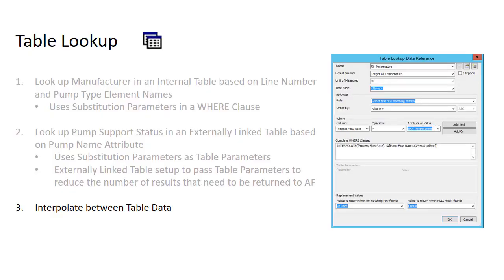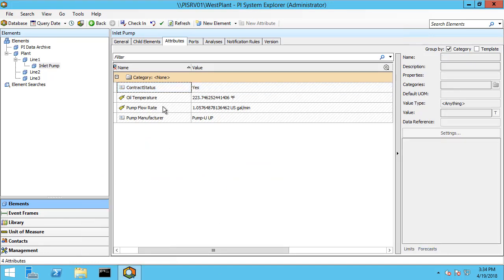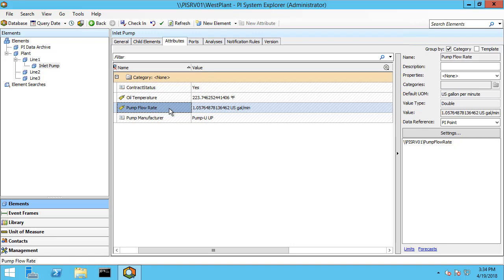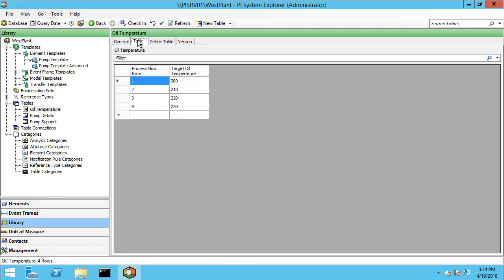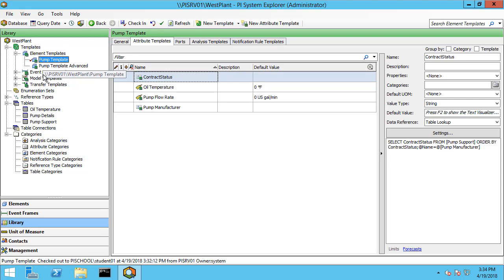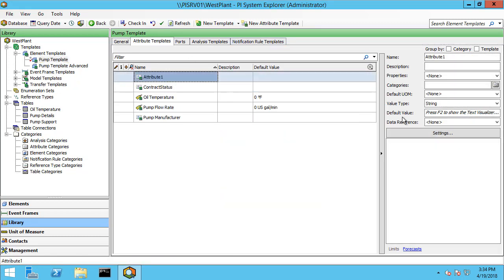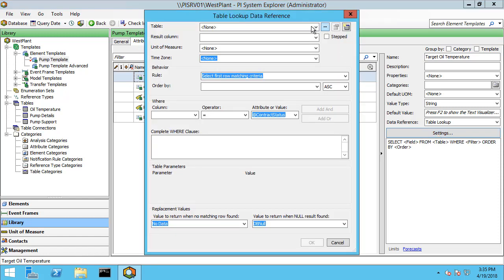Our third and final example is interpolating between table data. In PI System Explorer we have a pump flow rate of 1.057 and an oil temperature of 223. Based on the pump flow rate we have a target oil temperature, and that information is stored in a table. Let's go ahead and look at the oil temperature table. When our process flow rate is around one, our target oil temperature should be just over 200. However, we won't actually be able to look up a specific value because it would be very rare that our flow rate would be exactly one, two, three, or four. So instead we'd like to interpolate between those values.